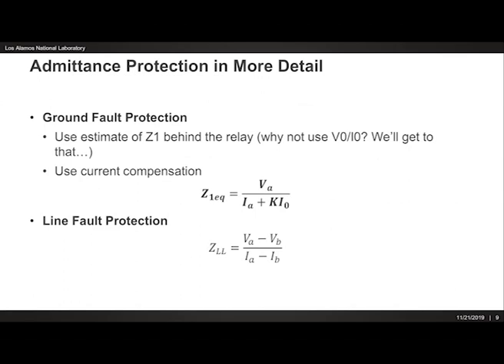Now that we know what's going on with the inverter, let's go into a little review of admittance protection. So I'm considering ground faults for this presentation. And in this case, I'm using admittance protection with current compensation. The top equation that we see is equivalent to measuring the positive sequence impedance of the line. In the case of line-to-line faults, ZLL is also equivalent to measuring the positive sequence impedance of a line during a fault.